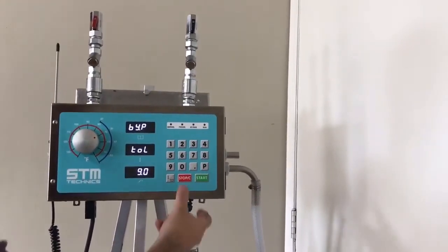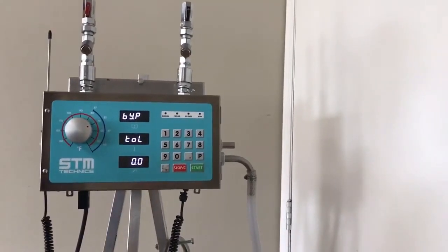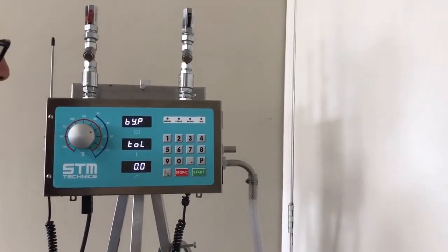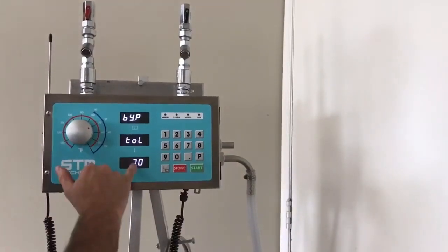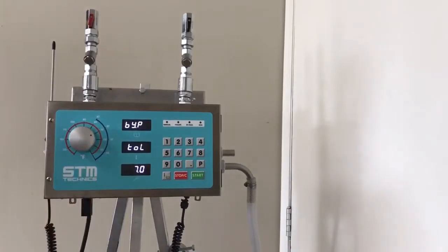To do this, we press the stop button, zero out our tolerance window. We're going to put in a tolerance of say 7 degrees Fahrenheit, so we press number 7. Now we're set for 7 degrees Fahrenheit tolerance within our set water temperature.